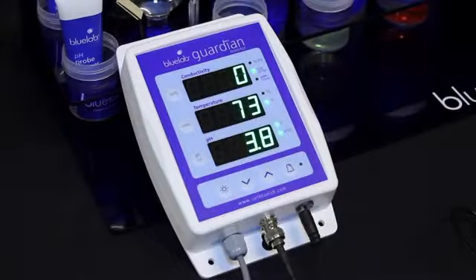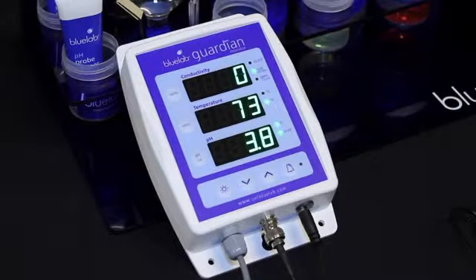Rinse the probe in clean tap water. You have successfully calibrated when you see both calibration indicator lights glowing. Discard all used solution after calibration. Never put them back into the bottle, as you will contaminate the solution. Clean and calibrate the pH probe once a month to ensure accurate readings.